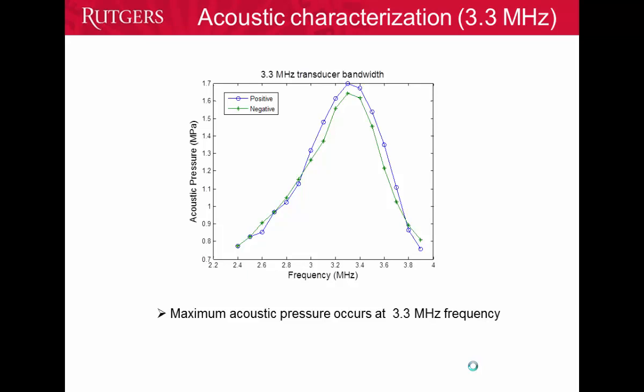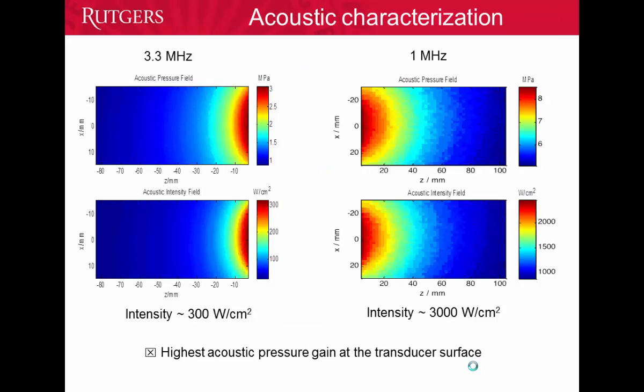The acoustic pressure measurement versus frequency for 3.3 megahertz shows that we reached the maximum pressure exactly at 3.3 megahertz. Sorry, megapascal. Then we measured the acoustic pressure field and acoustic intensity along the z-axis for the 3.3 megahertz and 1 megahertz transducers.